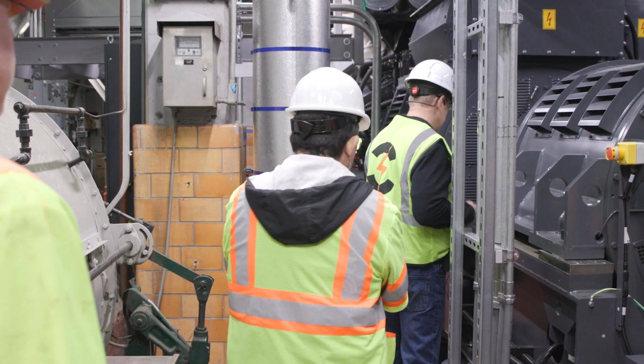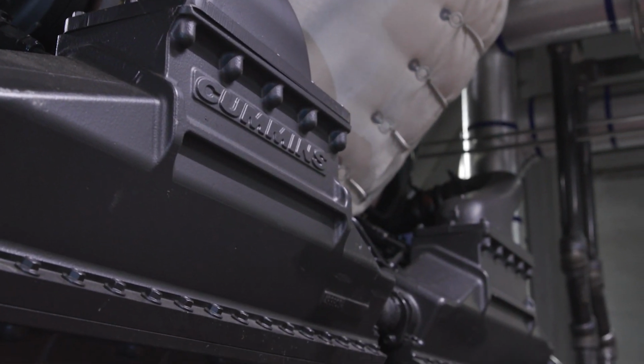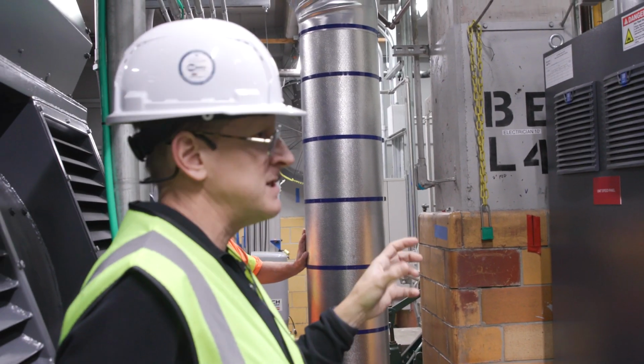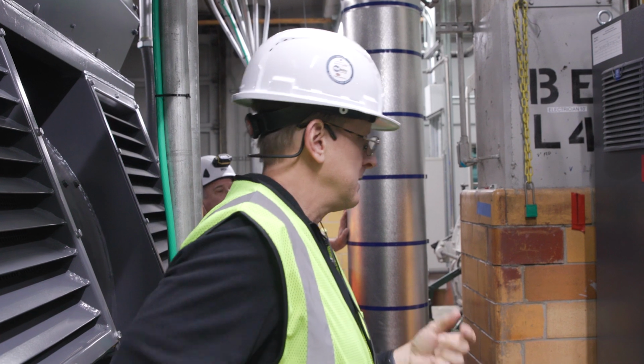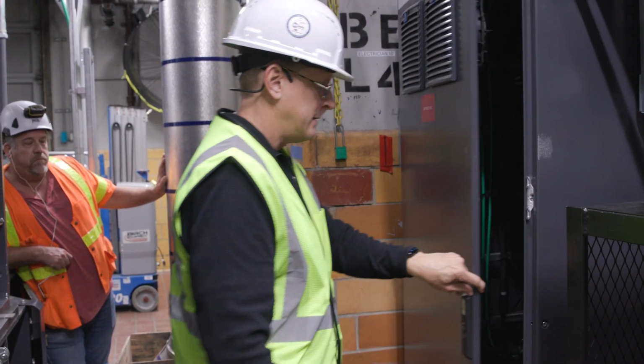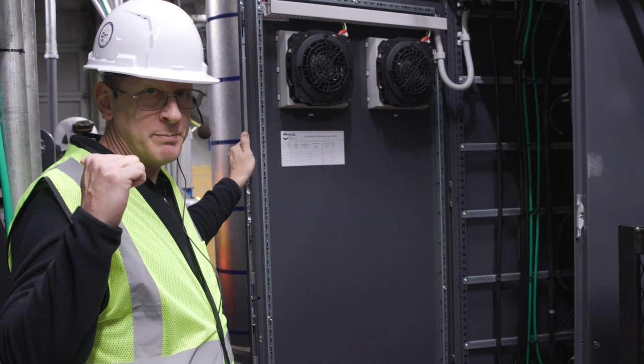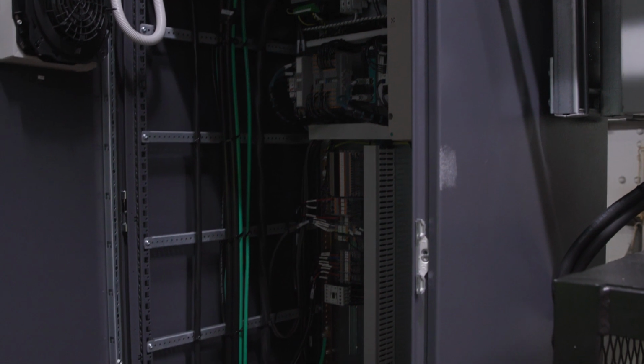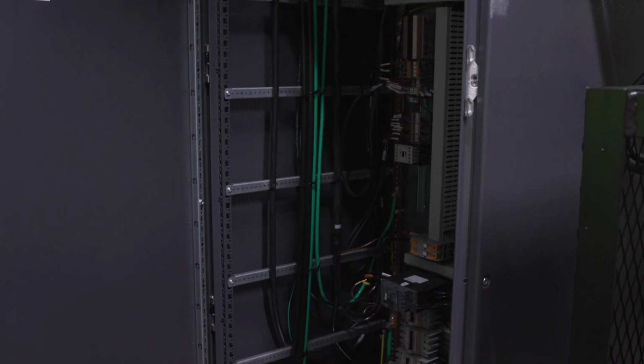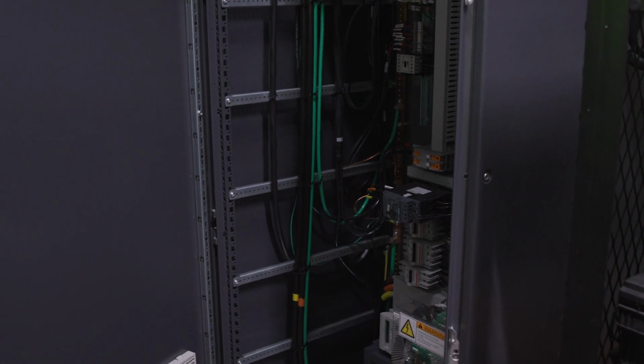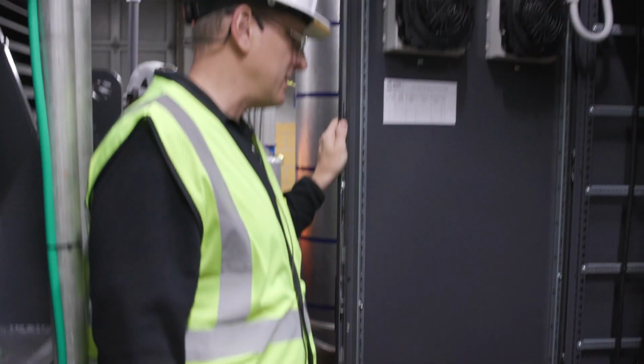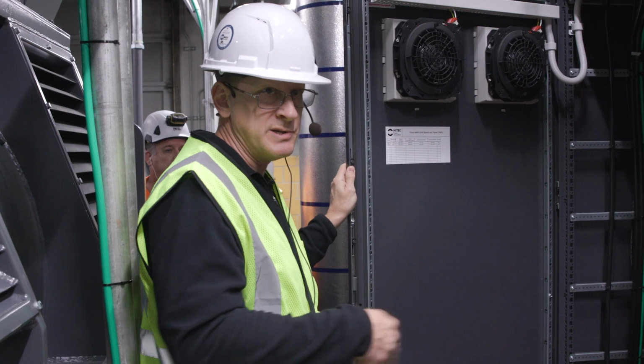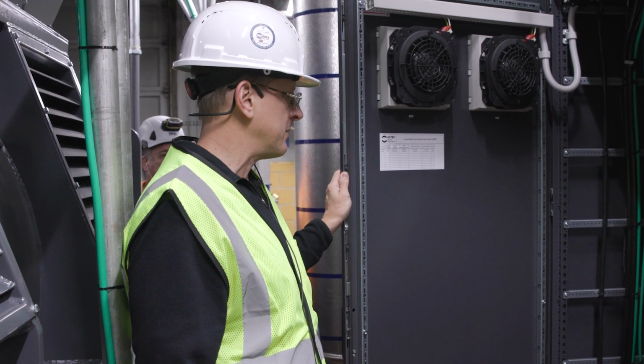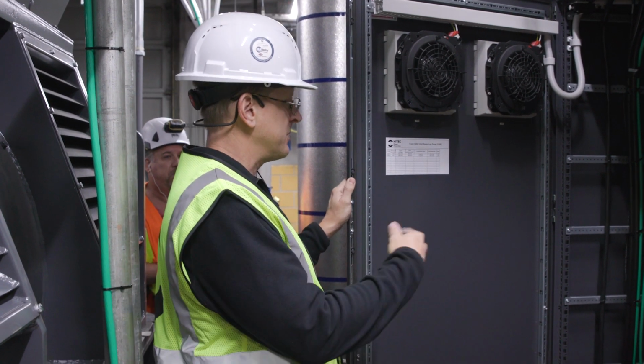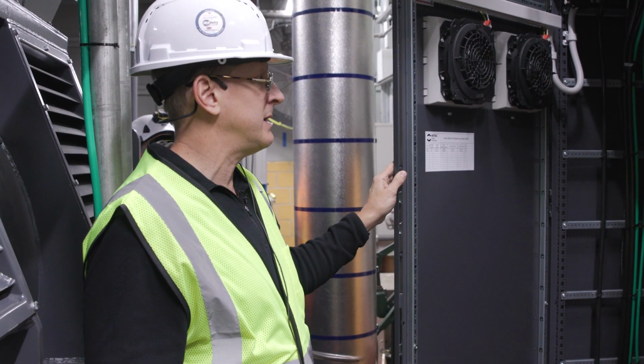Okay. Continuing to walk around, just want to bring attention first to the USP panel, unit speed up panel. Again, this is being fed from the ADP, critical 3-phase 480 volts. Inside this panel, you'll find the frequency drive for the pony motor. It's a Yaskawa drive, so it controls the pony motor itself. And then on the bottom right-hand corner, you'll see our rectifier, which sends DC current to the field winding of our DC excitation machine for actual extraction of energy. So this is the device that the PLC controls to extract the energy or to send DC to the outer windings of the outer rotor for extraction of energy from the flywheel. Of course, it has its own PLC interface card, so it can communicate directly with the PLC as well.